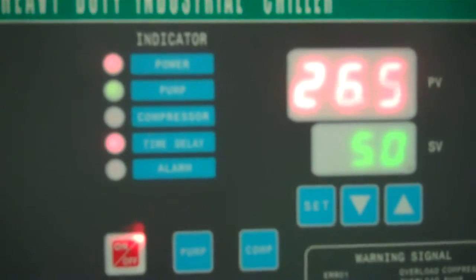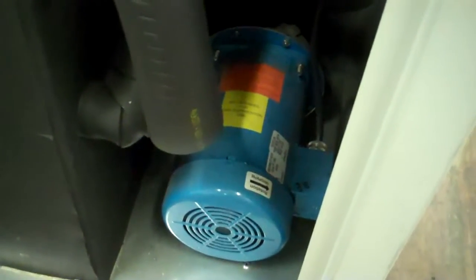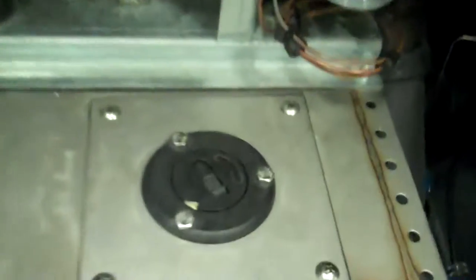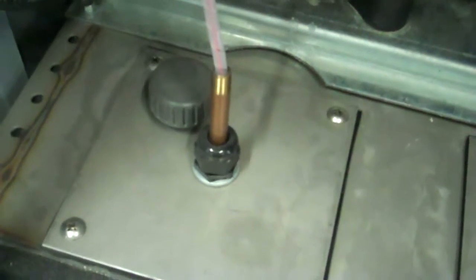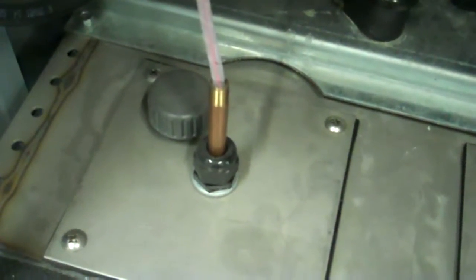First thing we do is we press the compressor button to start chilling, and it will go into a time delay, about 90 seconds or so. We have a 1 horsepower process pump, about a 48-gallon insulated tank. That's our fill area. That's our level sensor for the fill. The unit will shut off if the level gets too low, in addition to the sight glass that we have here.